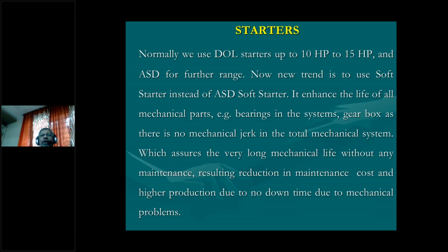Another important aspect I would like to highlight: if you see the catalog of the motor, the conventional motor, irrespective of efficiency, if you ask for a motor suitable for VFD, there is a separate range. The motor efficiency remains the same, the motor remains the same, but the bearings are insulated bearings. When you go for VFD, there is going to be a power quality problem, that is the generation of fifth harmonic. That is a different subject, so today there's no necessity to discuss that.